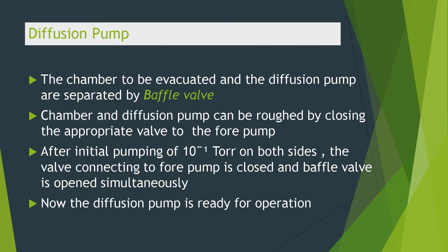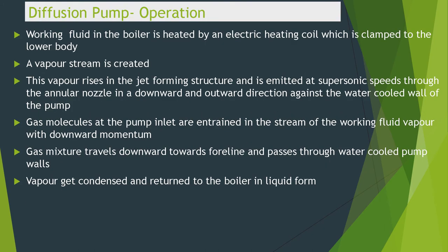Now the diffusion pump is ready for operation. The working fluid in the boiler is heated by an electric heating coil clamped to the lower body, creating a vapor stream. This vapor stream rises in the jet-forming structure and is emitted at supersonic speeds through the annular nozzle in a downward and outward direction against the water-cooled wall of the pump.